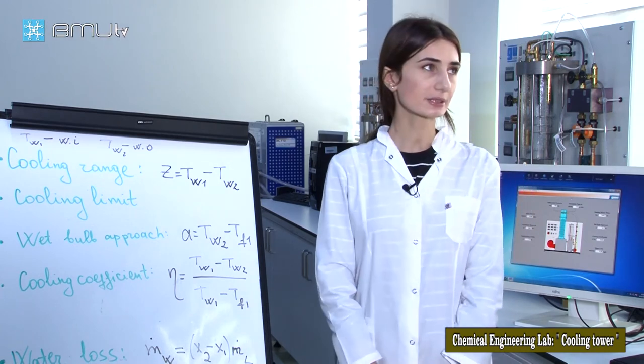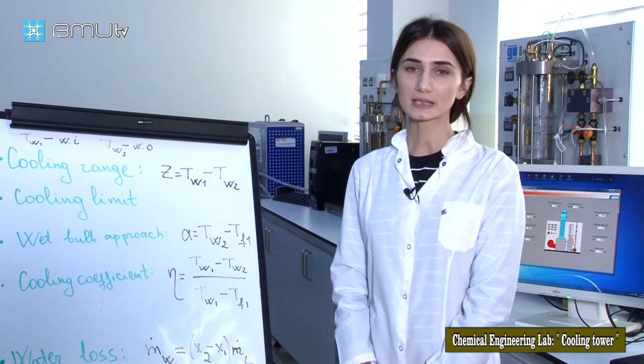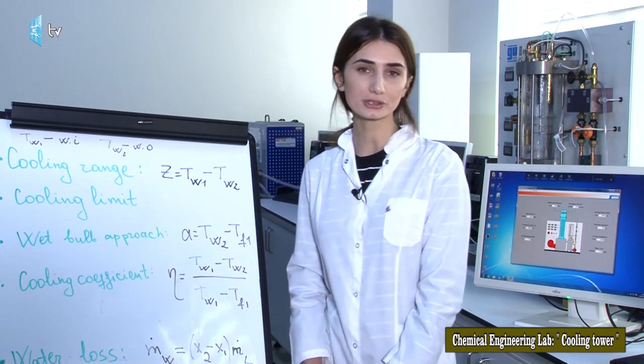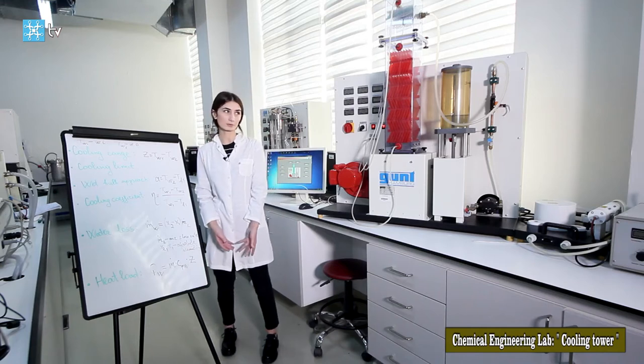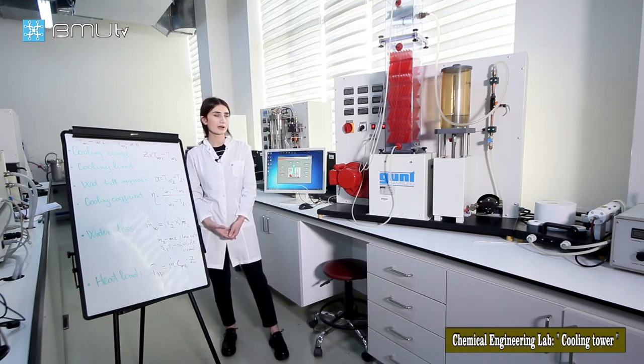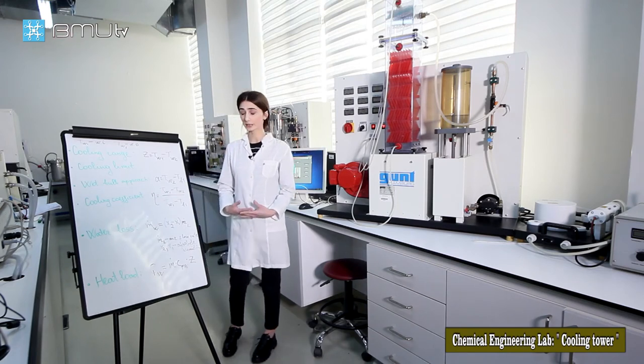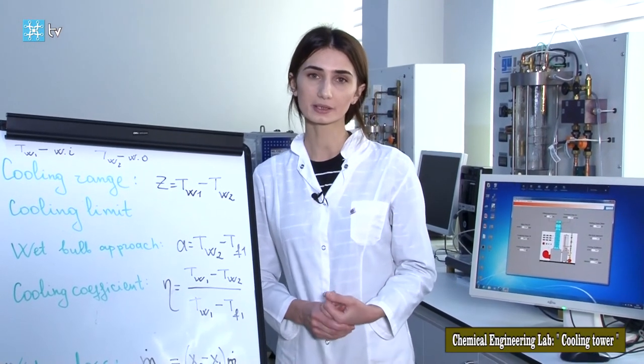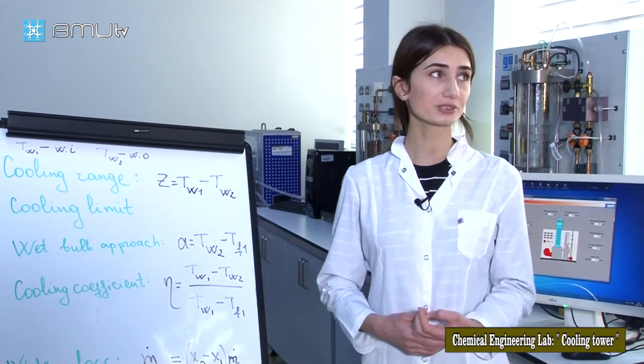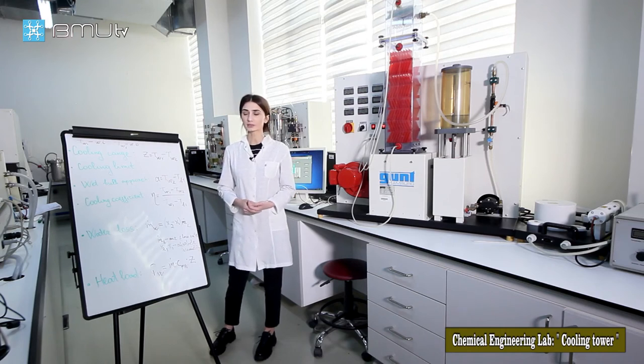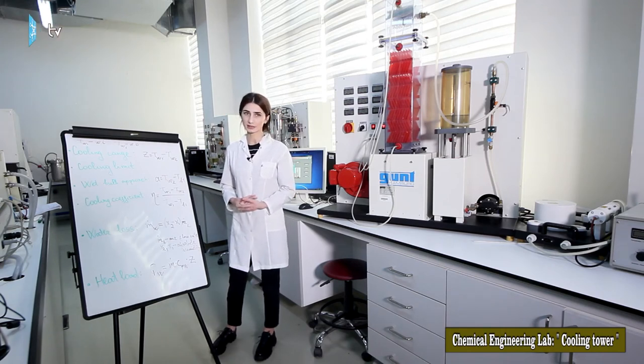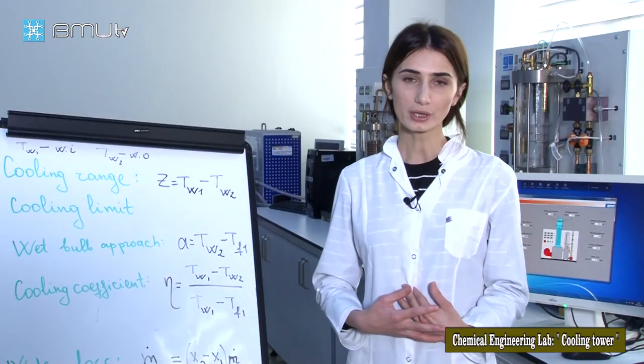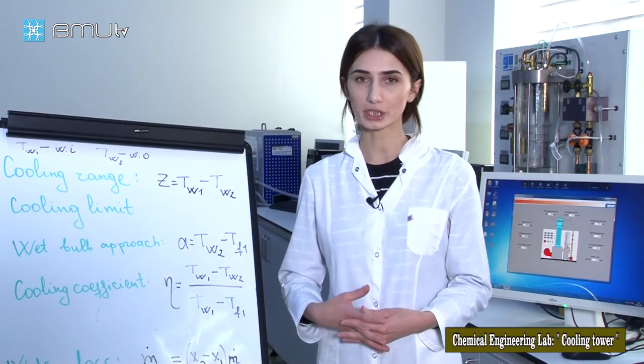The cooling limit and wet bulb temperature of air are the same — they show the lowest temperature achievable by evaporation. There is mass transfer because some water molecules are taken up by air, resulting in further cooling of the water. Air has some ability to take up water molecules, which causes a cooling effect. When the relative humidity of air reaches 100%, this air is called saturated air. Saturated air cannot take up water molecules anymore, and after this, cooling by evaporation cannot occur.